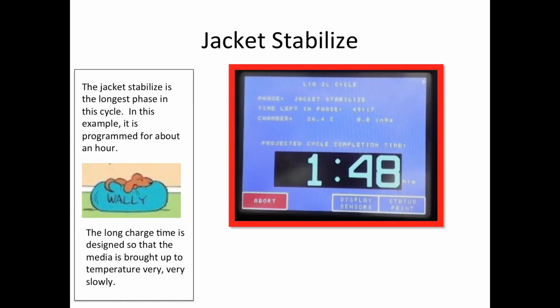The longest phase in the cycle is the jacket stabilize. It's programmed in this instance to last about an hour. Now, this very long stabilization time is designed so that our media in particular is brought up to temperature very slowly, which can be important for certain types of media. The jacket stabilize phase is also very important because the jacket is used for temperature stability. So if the jacket is not stable, then the autoclave sterilization chamber temperature will not be stable either.